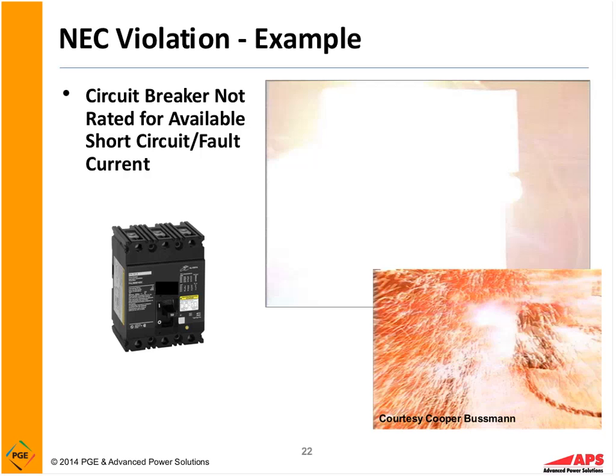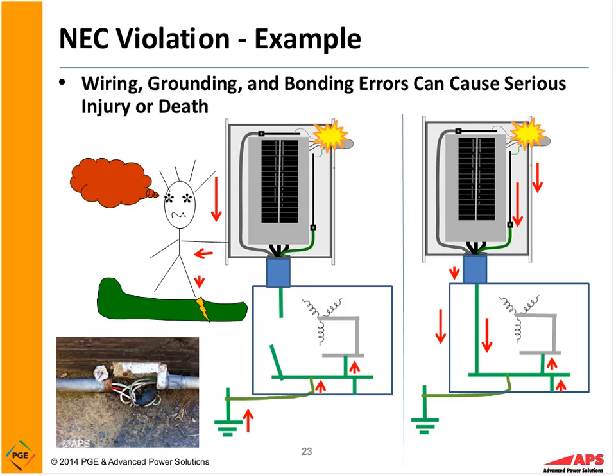So that's one example. Many, many cases when we do studies, we find underrated equipment. And many times we talk to folks in our classes and find people are not aware of this one requirement for the fault current rating of equipment. So here's just showing you an example where we have a ground wire, and I put my arrow right here, where the ground wire has been broken, or a system bonding jumper that's been broken here. So the ground wire may be left off, or it may have a loose connection. For whatever reason, it's not having the proper current flow through there.